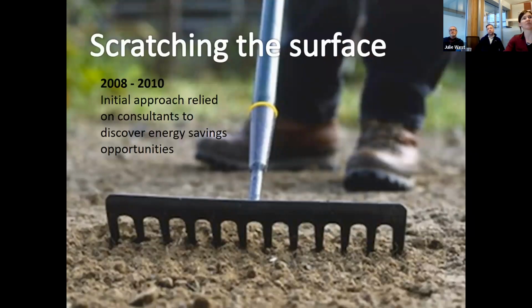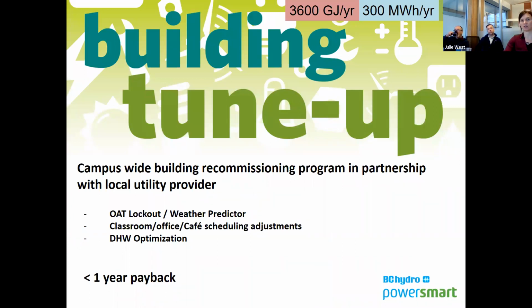So, scratching the surface for our department, when we started looking at this, our department relied on consultants heavily to discover energy savings opportunities. And we put it through the building tune-up program, or the continuous optimization program here, which is incentivized by BC Hydro, our electricity utility provider. And this program did some very initial savings with less than a 1 year payback through outdoor air lockout, weather predictions, scheduling adjustments, and a domestic hot water optimization. And it saved roughly 3,600 gigajoules per year, 300 megawatt hours per year, and roughly 3% right off the bat.